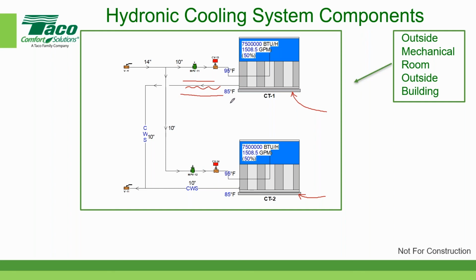Now, if you move to a closed loop cooling tower, in the wintertime, the cooling tower becomes a dry cooler. It's no longer evaporating water. You shut off the water evaporation, and now you can use glycol in a closed loop cooling tower. And if I put a heat exchanger over here, and let's say I put a pump, this is not the best diagram in the world, but you get the general idea here. If I put a pump over here and I pump to a plate and frame heat exchanger, then I can have glycol on the closed loop cooling tower side, G for glycol, and on the other side of the heat exchanger, I can have just straight water.